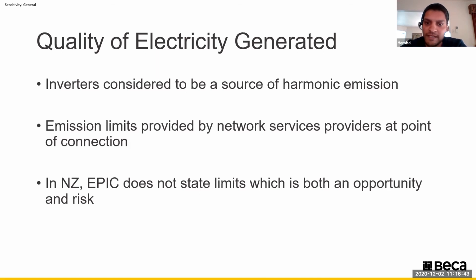In New Zealand, the Electricity Industry Participation Code does not actually state the harmonic emission and flicker limits at the point of connection. This is both an opportunity and a risk, as it makes it easier to navigate through the compliance requirements. However, the effects of power quality issues due to harmonics are observed locally, and if people start to complain about power quality issues, it'll be up to you as the asset owner to rectify it to an acceptable limit.